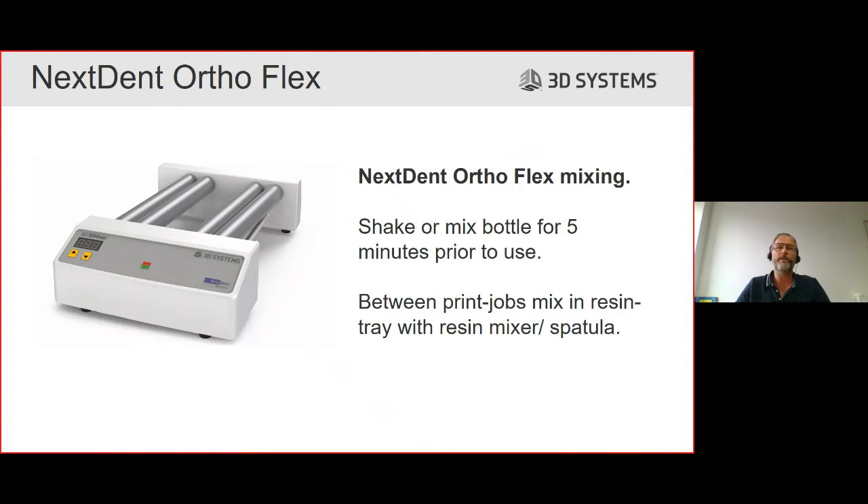When using NextDent material, we always have to mix it. The good news is that Ortho Flex is very easily mixed. The instructions for use say you mix it either by hand or on the mixer we provide for only five minutes. So before getting started, it only takes five minutes to shake the bottle - this material is always ready to print. It is not like some other materials that require mixing for at least two and a half hours for the first use. We do advise you between print jobs to mix the resin in the resin tray to check if there are no foreign bodies that could be harmful for the printer, print process, or membrane.